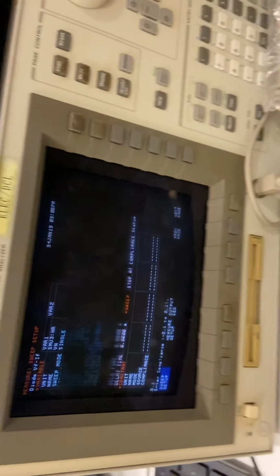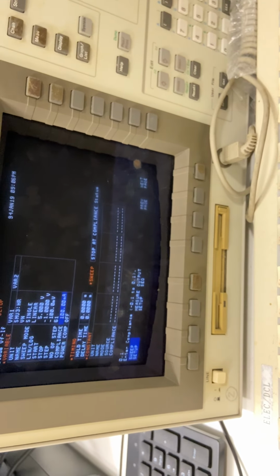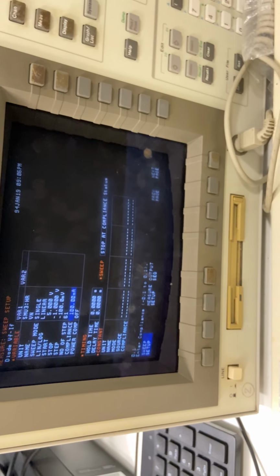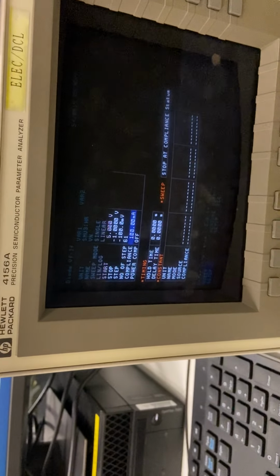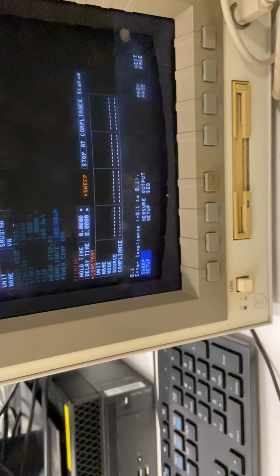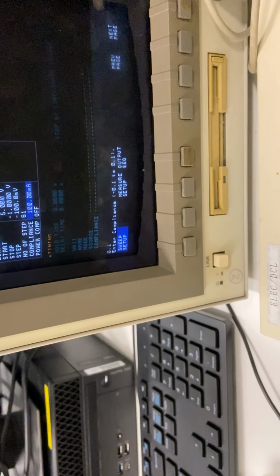Compliance is important actually. When it's doing measurement, if for whatever reason the current is very high and the voltage is kind of high, it will output a pretty big power, so there's a possibility that you will burn the device. If you're inputting voltage and the current is coming out, you can put a compliance there, which basically means you clamp the current. It will not allow the current to go above that value.